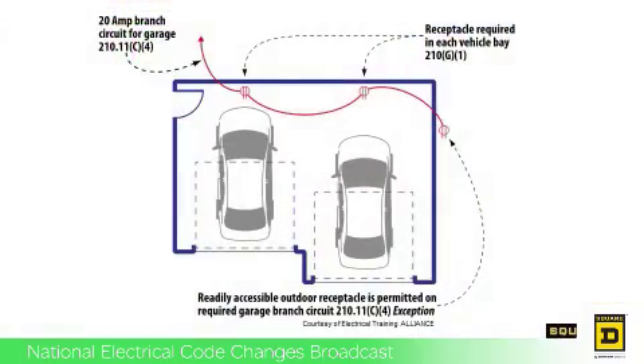Yeah, thanks, Phil. Panel 2 acted favorably to strengthening the requirements for branch circuits that supply dwelling garages, and it relates primarily to more power capacity. In this section, the code used to allow a general purpose 15 ampere 125 volt branch circuit to supply not only the garage, but it could extend beyond that and supply other areas of the home. It got a little more restrictive this cycle in that now the receptacle outlets in the garage are required to be supplied with a 125 volt 20 ampere branch circuit.